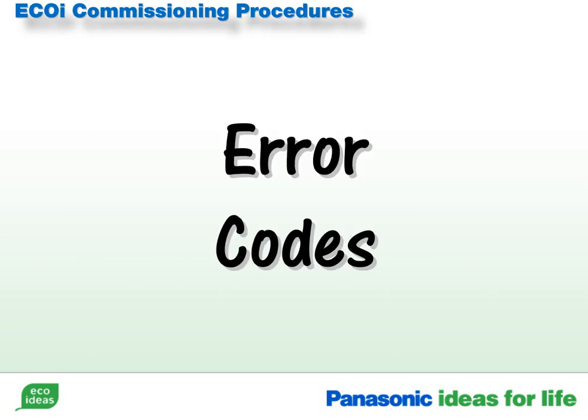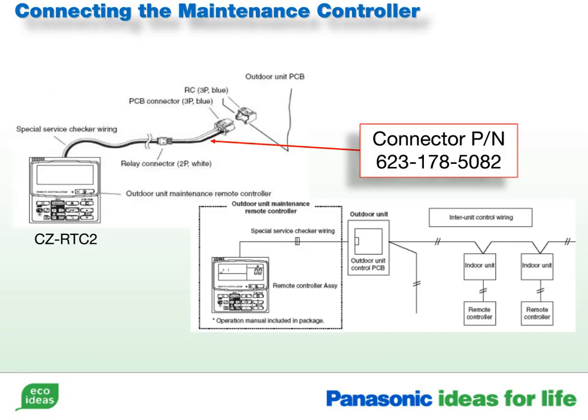How to retrieve error codes and their meanings. There are 2 ways to retrieve error codes. You can either use LEDs 1 and 2, or by plugging in a CZ-RTC2 into the main board in the outdoor unit. If you choose to use the latter, you will need the maintenance controller wiring harness. The part number is 623-178-5082.